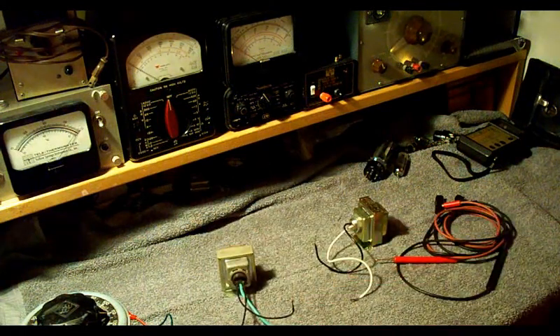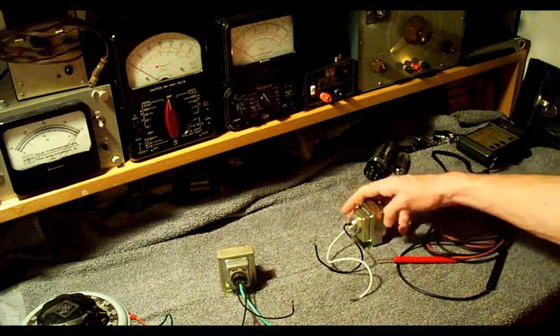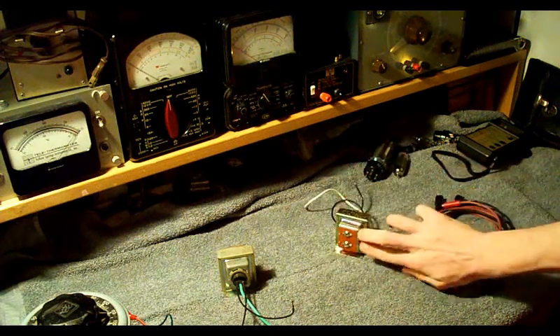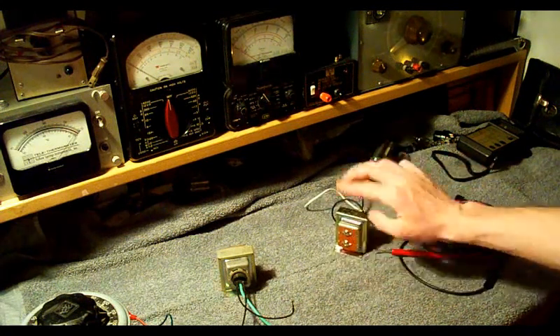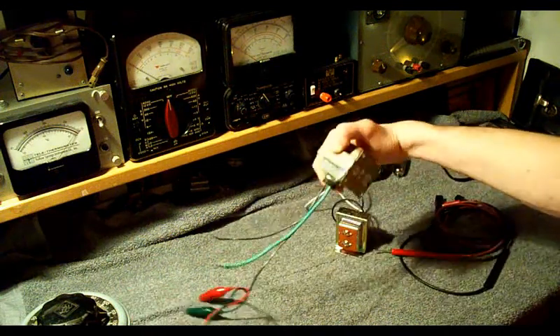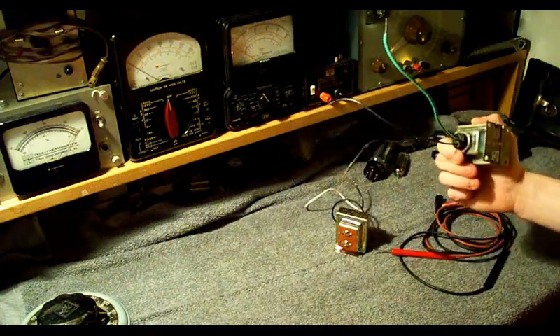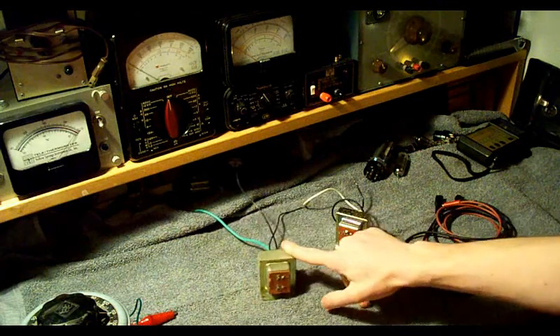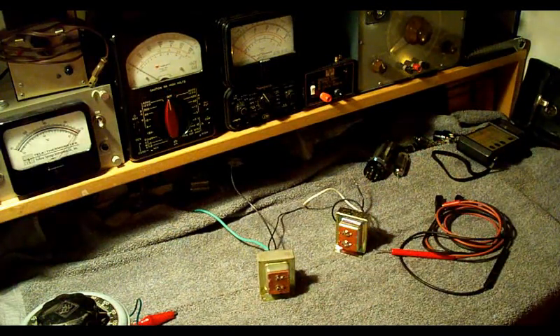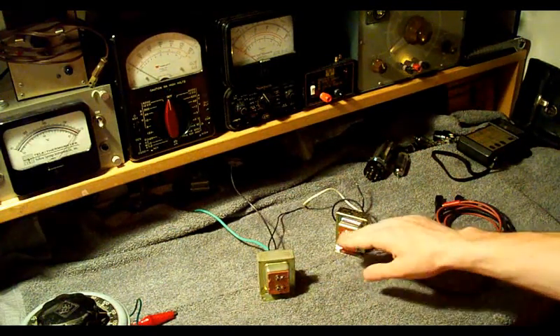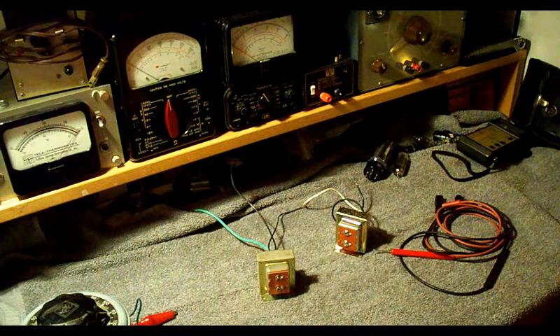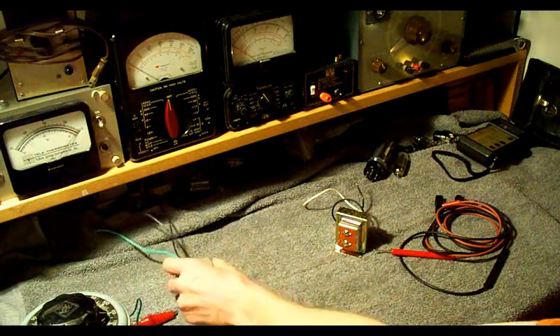The secondary winding, or the output winding, is where either the stepped up, or in this case the stepped down voltage, or the lower voltage, will be outputted from the transformer. And in this case it is outputted on two screw terminals. These two particular transformers are designed to be used primarily on a doorbell type application. Anywhere from 10 to about 15 volts AC should be outputted at these screw terminals. So I'm going to show you how to test these transformers today.